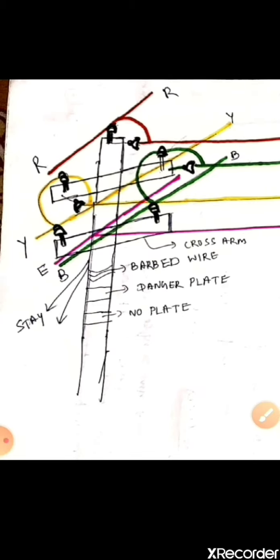So the new arrangement we have done is we have connected one new cross arm, this is the cross arm, and we have connected two new pin type insulators. Now the new R phase line is connected to this point of the pole through this insulator. Again the Y phase line is connected to the new cross arm through this insulator. Again the new B phase line is connected to the new cross arm through this insulator. Now the R phase line, the live line, the connection is taken from the R phase line to the new line through this jumper wire.